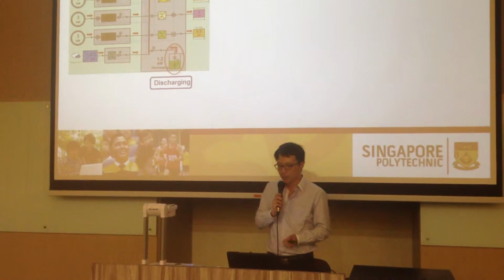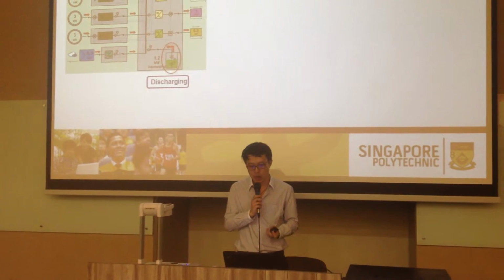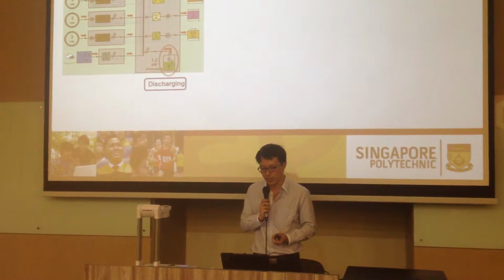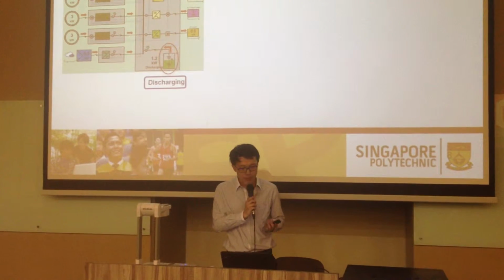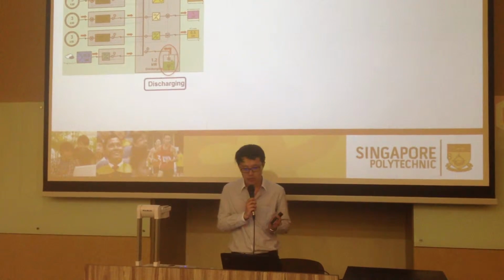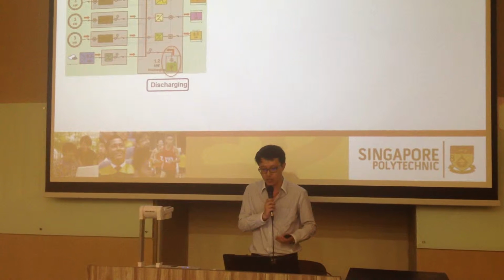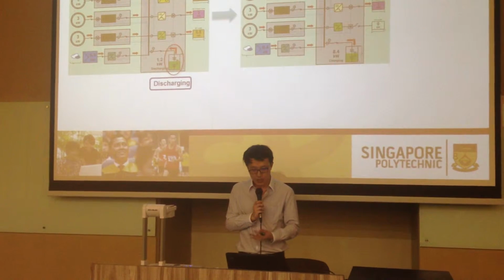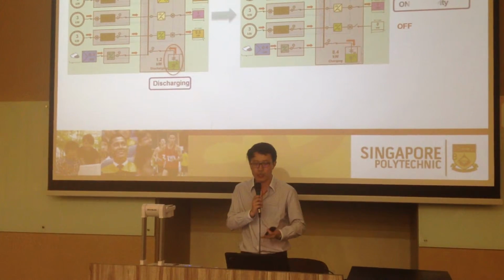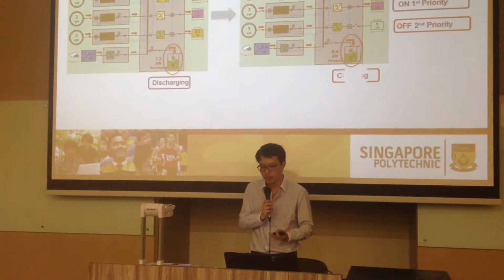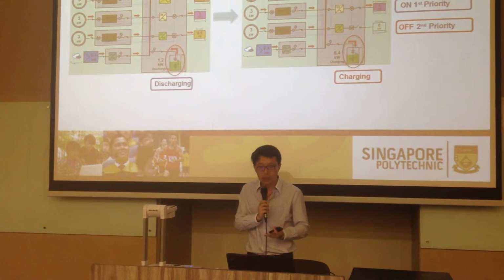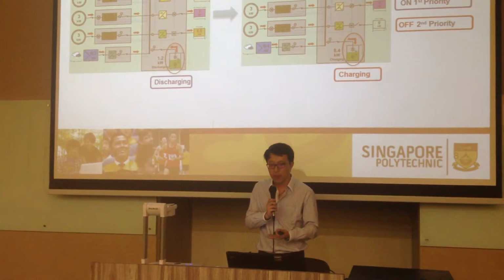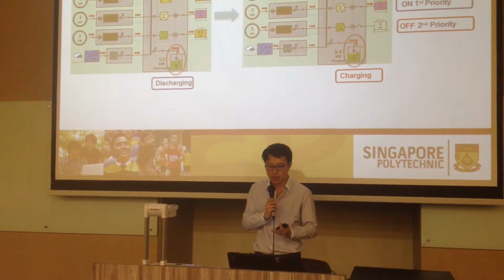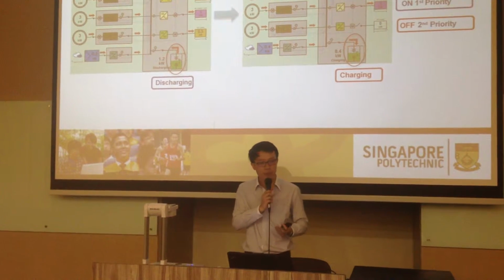The second feature is battery charging control and assignment of load priority. The system keeps tracking the battery charge status and charges the batteries if they are not fully charged. Once the SOC is below a specific value, for instance 50%, it will cut off all non-critical loads to ensure supply for the critical loads and charge the batteries to maintain system stability.